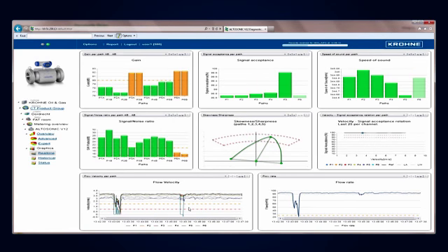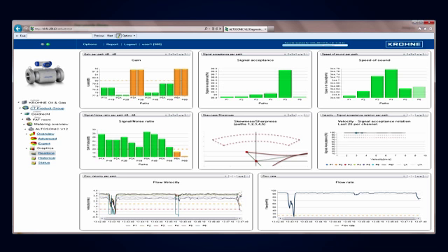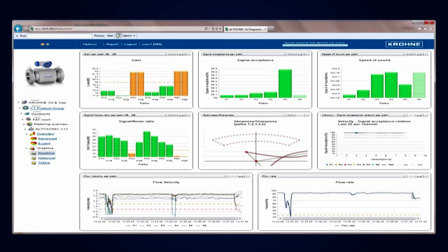Air is being sucked through, so the fan is sucking air through the meter. We block the bottom of the meter on the inlet side, and immediately you see the flow velocity starting to change. The flow profile has been very upset. Also, the flow rate starts to drop because part of the inlet has been blocked by a piece of tape.